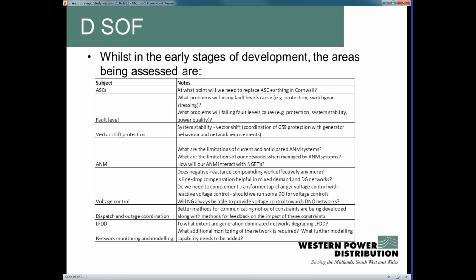One thing we've found in Cornwall is that it's very dependent on the impedance of the network, which changes as equipment connected to the network changes. As we've connected more cable in Cornwall, we're seeing increasing issues with that form of earthing, and there will come a point where we need to switch to a more conventional form used elsewhere. We need to understand the right economic point to do that, which would form part of this operability framework.